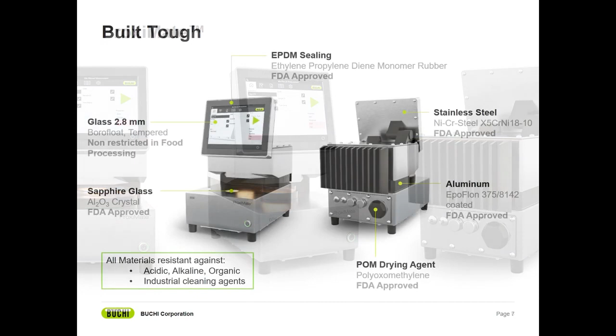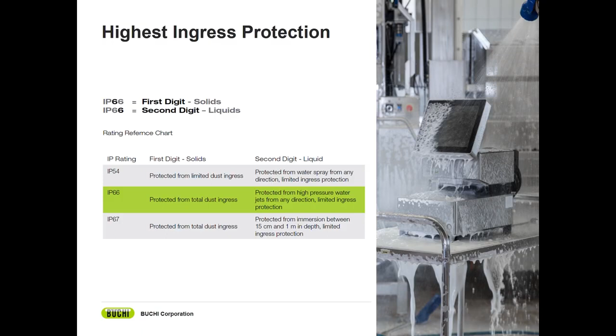Number one comment we received from customer feedback is the focus on durability and uptime. And our team really felt strongly that this should just be standard as opposed to an optional line item. Without question, our goal was achieved here. This is the first NIR ever built with an Ingress Protection 66 rating. With FDA approved seals and metal building materials, this instrument is really stitched up to take on the worst environments. You can literally get this instrument dirty and spray it off with a hose or wash it down like you would your car. Though I'd advise probably not walking it through a car wash.